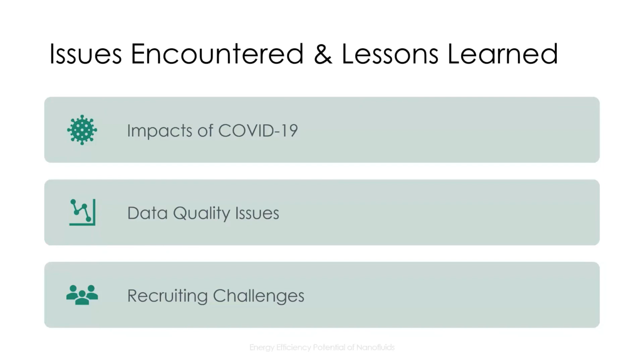The varying levels of data access inhibited our ability to do some troubleshooting of data in real time, and that led to some data quality issues. The varying types of data available through the building automation systems also skewed results to a degree. And again, going back to the example of the difference in how we calculated chiller power input between the water-cooled and the air-cooled chiller.